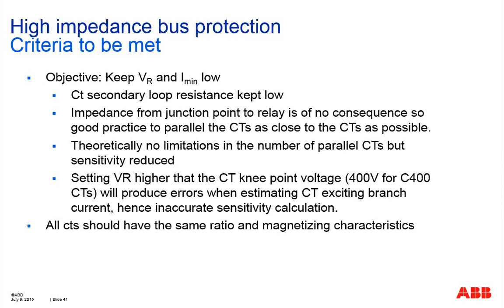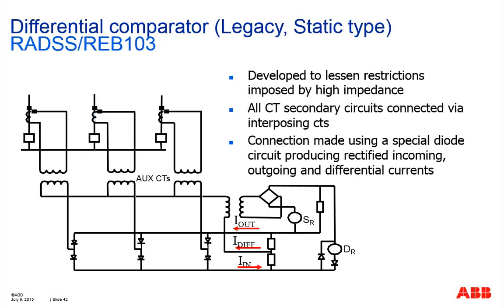And the other limitation or rule for high impedance busbar protection is that all CTs should have the same ratio. Next, we gradually migrate into some of the modern low impedance type of relay design, and I'm not going to focus too much on this, because this really is an ABB design of the very old, proven, reliable RADSS.